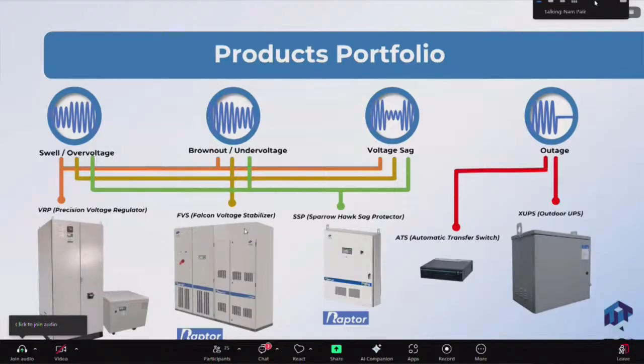The next product here, I won't mention it too much. This is just a large three-phase voltage regulator going up to about a megawatt, Falcon voltage stabilizer. And then we have a Sparrowhawk sag protector. It can take a sag of minus 50% for 7 seconds. And it has a lot of capacitors inside, and we generate AC power to fill in what's missing during those 7 seconds using this voltage Sparrowhawk product.